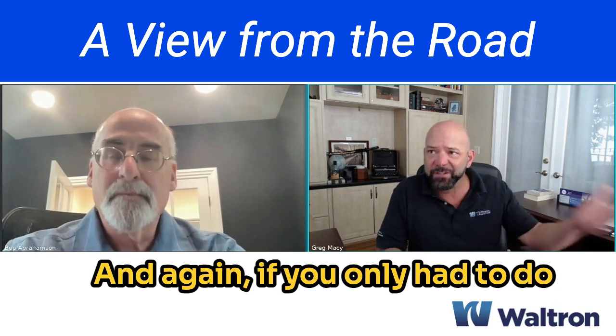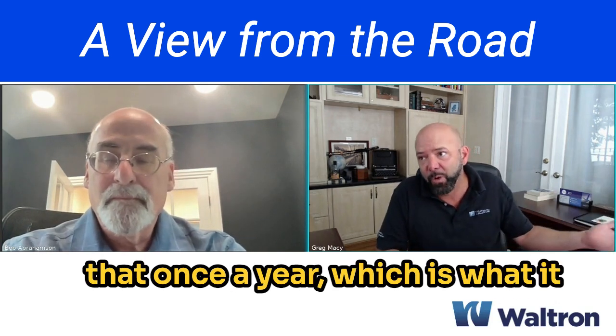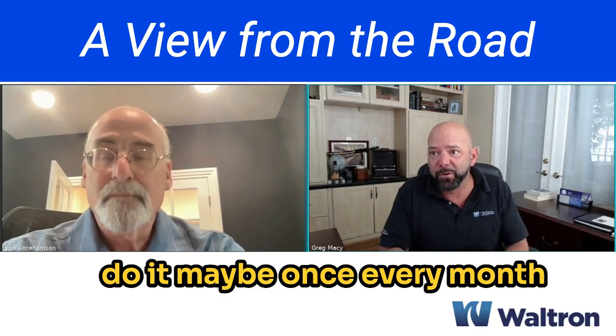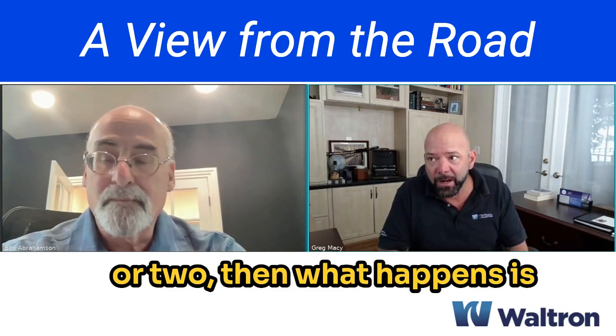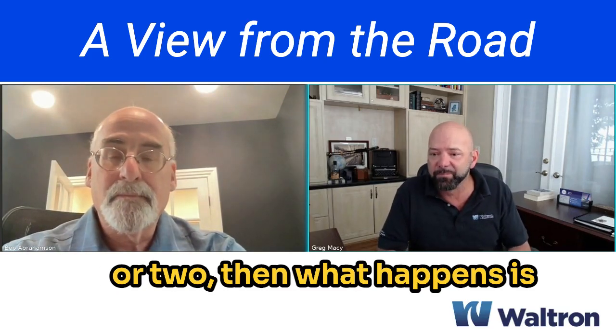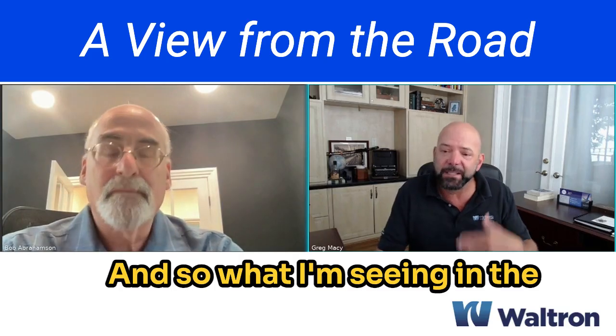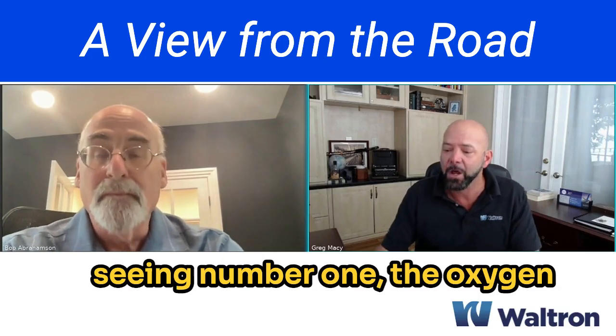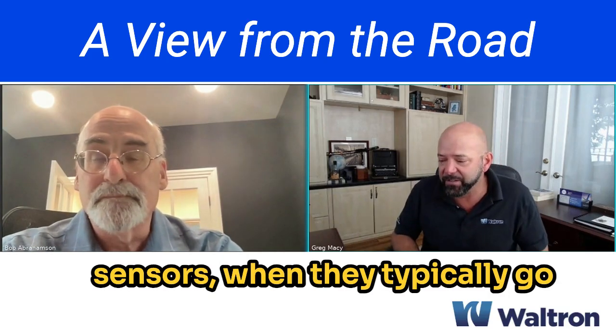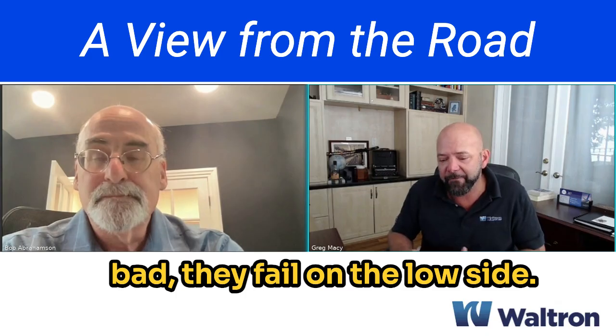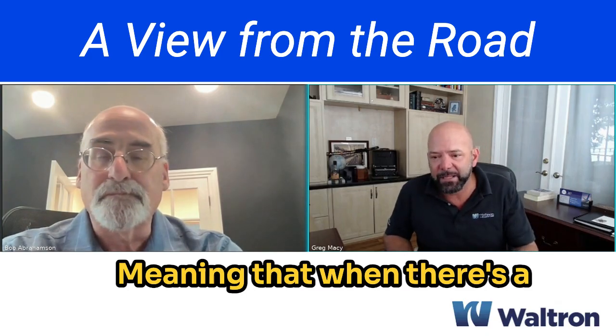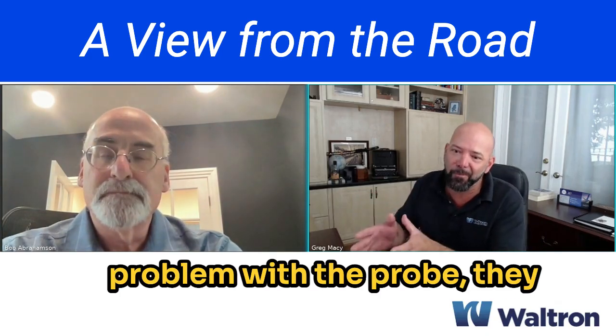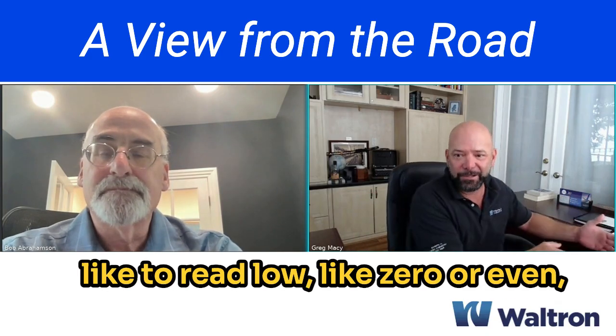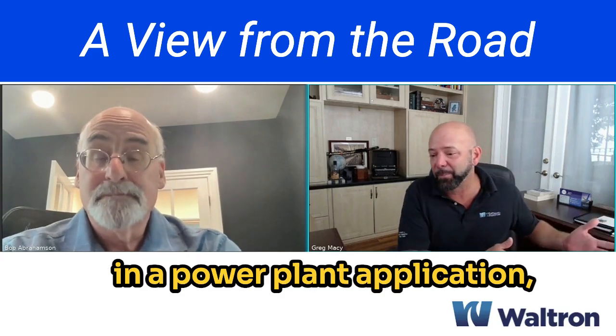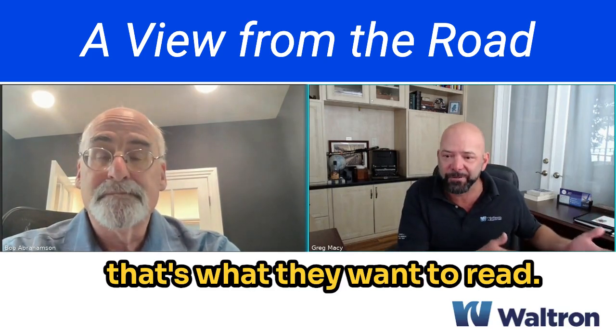And again, if you only had to do that once a year, which is what it used to be, and you now have to do it maybe once every month or two, then what happens is people just don't change. And so what I'm seeing in the field is, number one, the oxygen sensors, when they typically go bad, they fail on the low side, meaning that when there's a problem with the probe, they like to read low, like 0, or even in a power plant application, that's what they want to read.